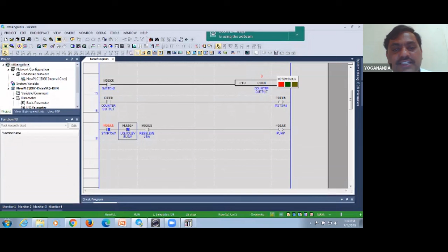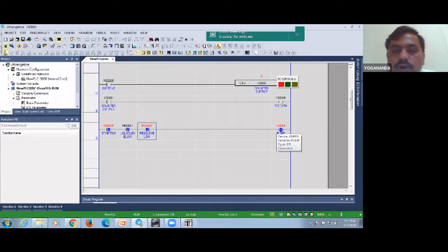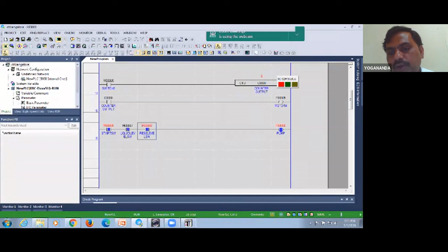This is the logic. If all the conditions are high except the liquid status in the tank, then only you can start the pump. You can see now the start switch is closed. We have sufficient liquid in the reservoir, and the liquid level switch is below the reference line in the tank. So 0 will be complemented to 1 because it's a normally closed contact switch. So this is 1, this is also 1, and this is also 1. Then you can start the pump to pump the liquid from the reservoir to the tank.